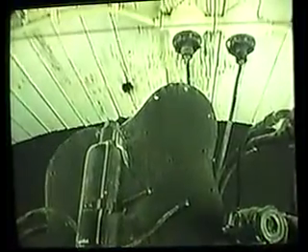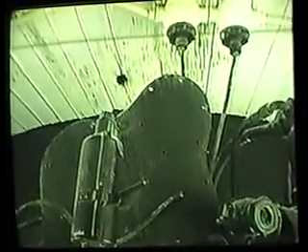Then you can shut down your injectors. Once they're shut down, check your gauge, make sure that you're still getting air from the house line or steam. Keep your pressure up at about 60 pounds.